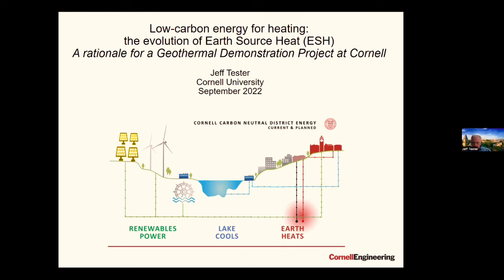To put this in real numbers, it's about 50 megawatts or so is the base heating load for the campus. But on the 20 or so really cold days in winter, it can go as high as 80 or 90 megawatts. The electric load's about 30. So it can be more than double, maybe even 3 times the electric load on campus. The cooling load, because we live in a colder climate here, is a lot less than the heating load, and we can take care of that with the lake. So that's sort of the idea here.